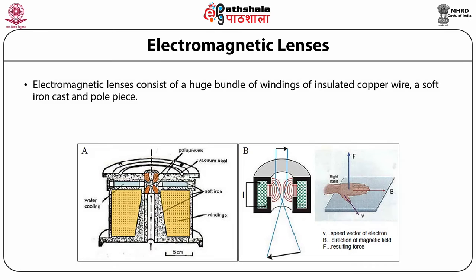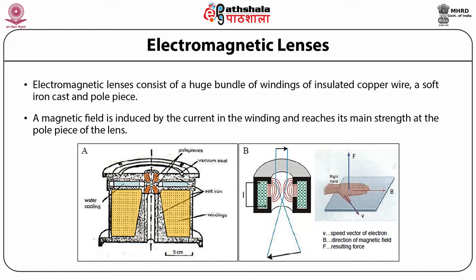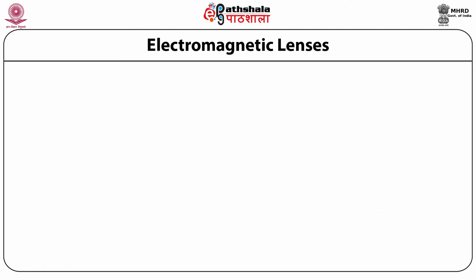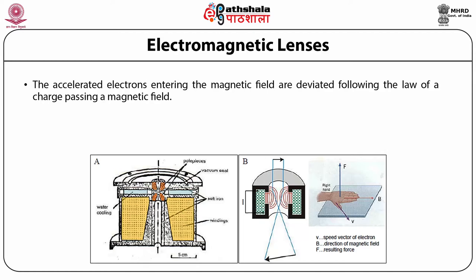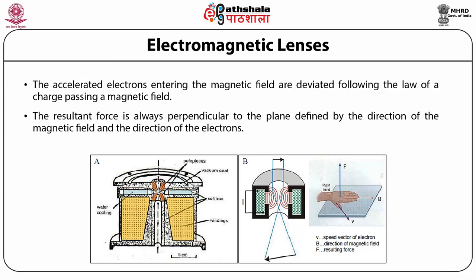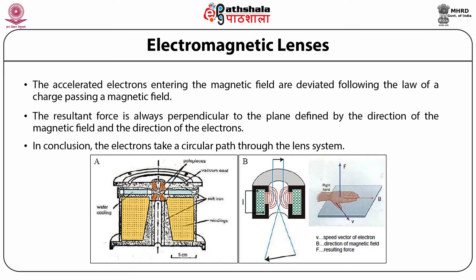Electromagnetic lenses consist of a large bundle of windings of insulated copper wire, a soft iron cast, and a pole piece as shown in figure A. A magnetic field is induced by the current in the winding and reaches its main strength at the pole piece of the lens. The accelerated electrons entering the magnetic field are deviated following the law of a charge passing through a magnetic field. The resultant force is always perpendicular to the plane, so the electrons take a circular path through the lens system.